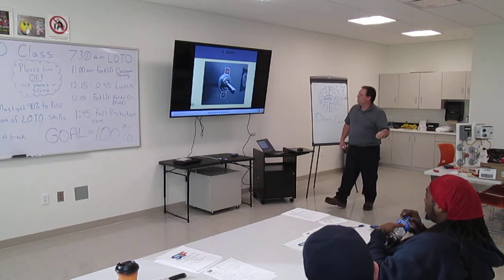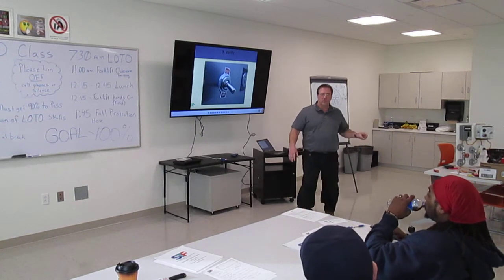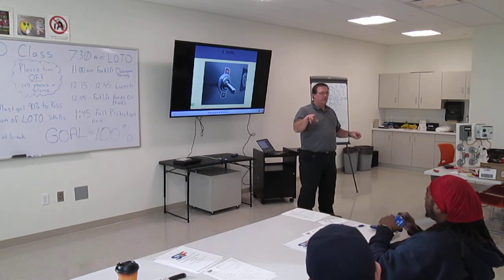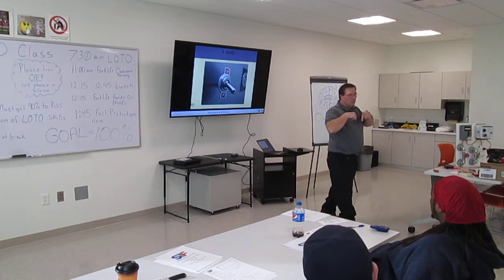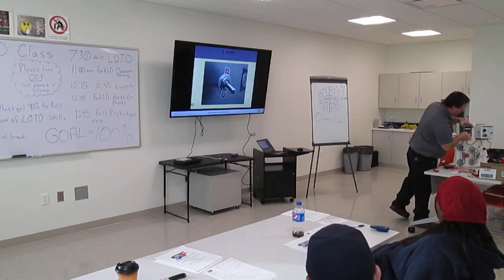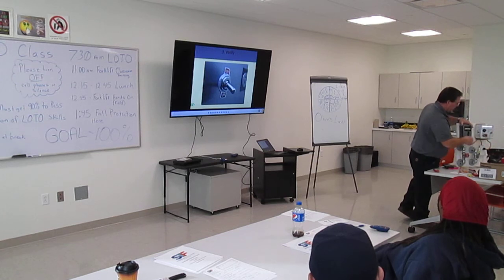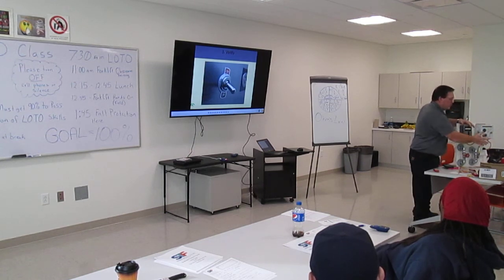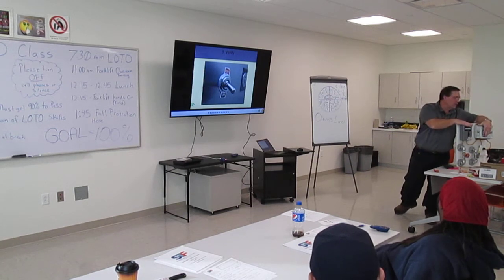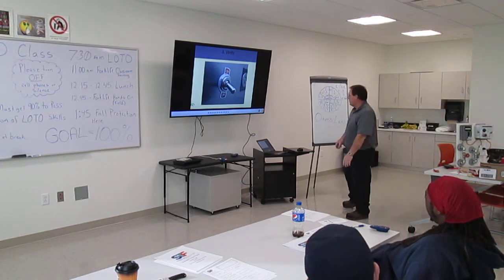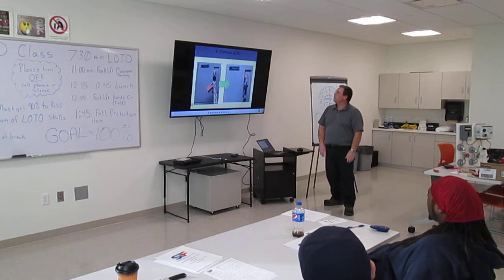Verify. What am I doing? Verifying all switches are in the off position. Exactly. Those switches you tried when you went to test it, make sure you turn them back off. If I do this lockout tagout, shut it off, lock it out, do all my work, and go to test it, oh yeah, it's still okay, good, I can do my work. But I don't push that back in before I re-energize this whole thing. This one doesn't work that way, but if it's a maintained switch, it can just start up by itself. Verify your switches and your controls are still in the off position.